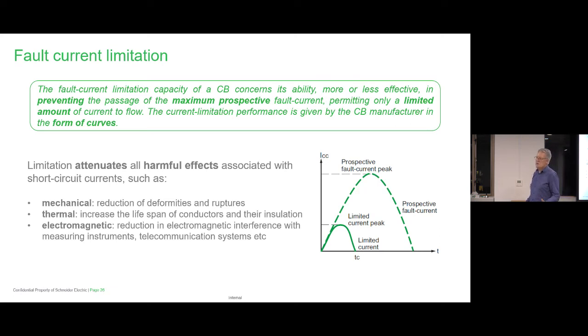You've probably seen videos of some of these short circuits. You've seen videos of switchboards being tested in Sydney, etc., and you've seen the big bangs. The switchboard is being put through a lot, but it's the protection devices that have got to be able to withstand it as well within that board. A lot of deformities can happen. The busbars can start to twist if they're not supported correctly. That's what they do on the switchboard in those tests. So being able to limit the current quickly limits the damage that can occur wherever this is happening, in the main switchboard, in the DB somewhere, to the cables that are connected. So the quality of the fault limiting breaker is very important.